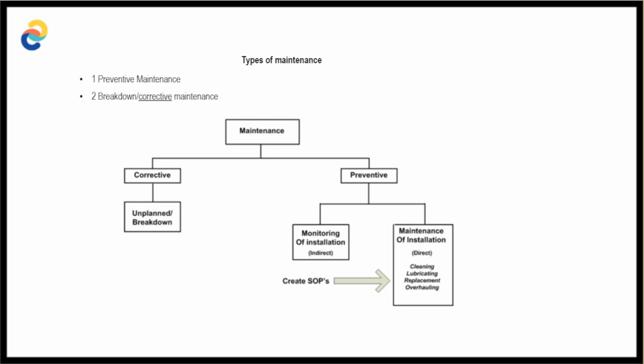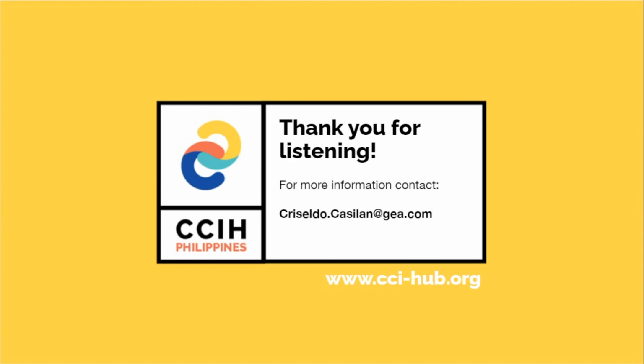Next is monitoring, whereby by constantly checking the parameters like pressure, temperatures, and other data, major faults that are slowly developing can be detected in time. Some examples of this are visual checkup, checking for unusual sounds, cleaning of filters, and checking of pressures and liquid levels. We can also use SCADA or Omni to check if we are still operating in the proper condition. Well, basically that concludes my presentation for the safety and maintenance.